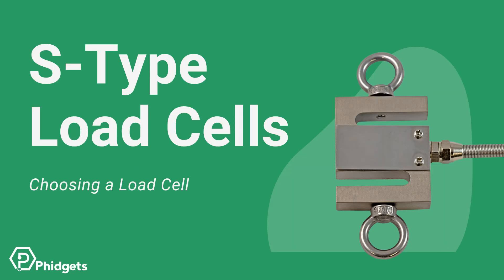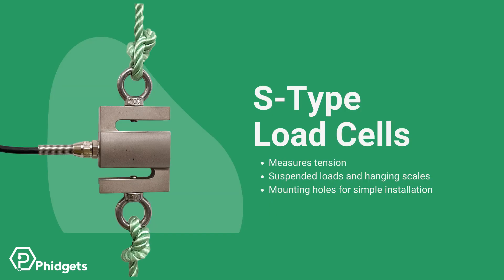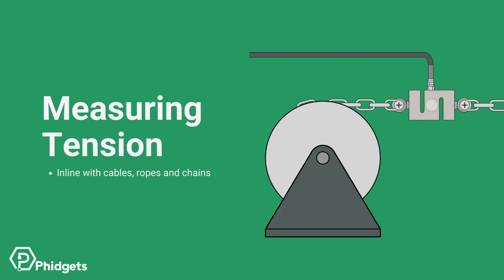The next type of load cell is the S-type load cell, easily identified due to their S shape. These load cells are primarily used to measure tension, which makes them ideal for applications with suspended loads and hanging scales. Installation is easy due to the mounting holes on the top and bottom — eye bolts or rod end bearings can be easily attached and provide a connection point to the rest of the system. Some applications include monitoring tension in cables, ropes, and chains, such as on a winch or a crane.